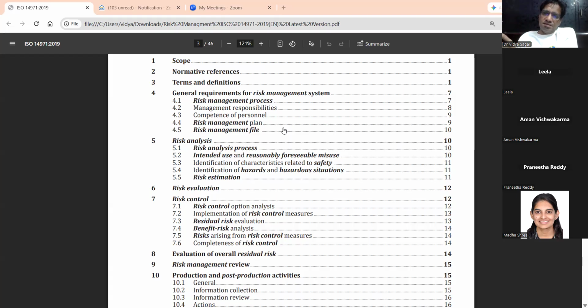And in residual risk, you need to discuss each and every residual risk. It's not like we have risk controls and we have controlled the risk and say that this residual risk doesn't cause any further risk. That's a very wrong statement. You need to explain what this residual risk is further when it translates into the clinicals, okay, for that particular intended use. What risk can it cause to the patient? Of course, they are residual risks, but still, can you bring down the residual risk? Okay, is it possible, as low as possible? Yeah, that's a very serious question that has to be debated.